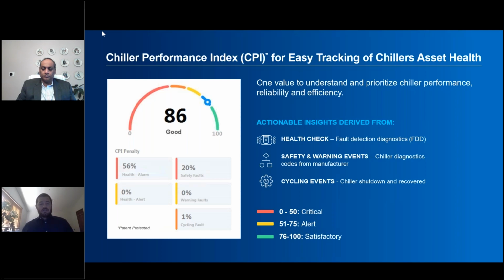There are 3 items we take into consideration when deriving the CPI number. The first is what we call the health check. This is a proactive way to look at your chillers through our fault detection and diagnostics, FDD — is my equipment operating the way I expect it to under a set of circumstances? Your chiller may be operating and meeting set point, but is it operating the way we would expect it to? That's the proactive approach.